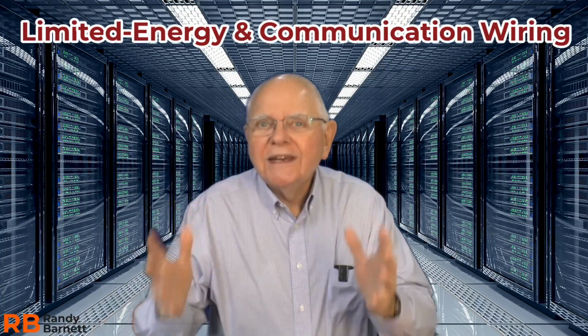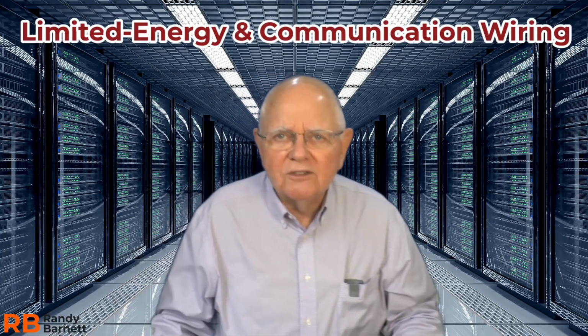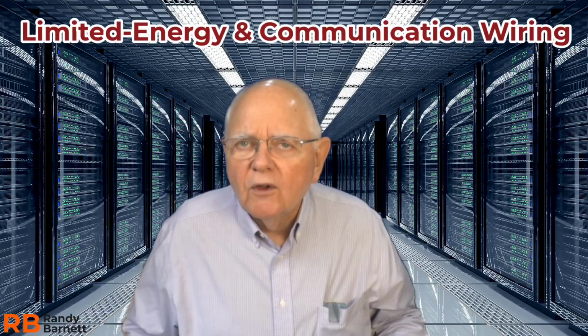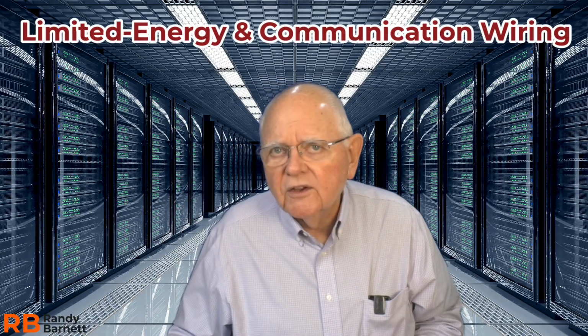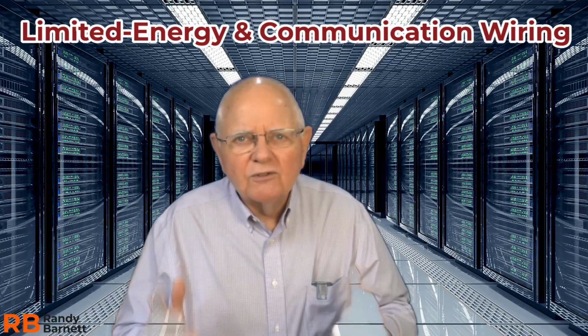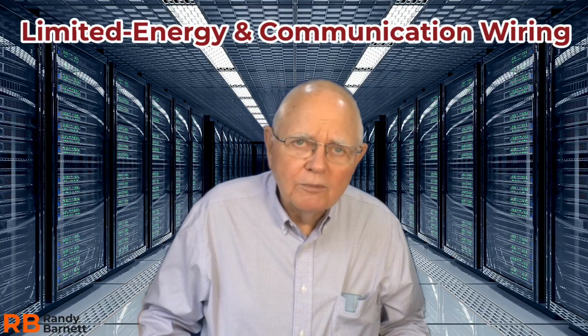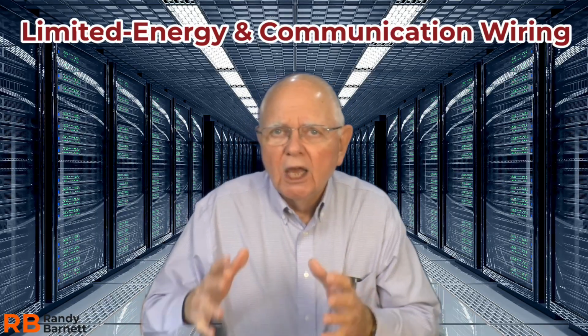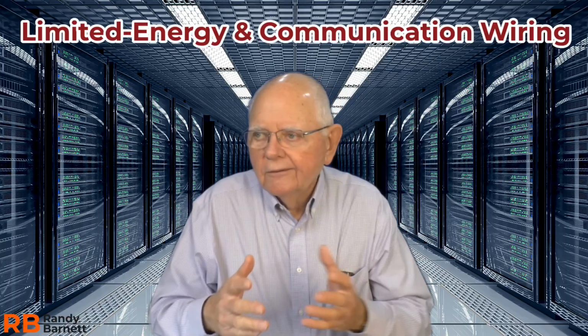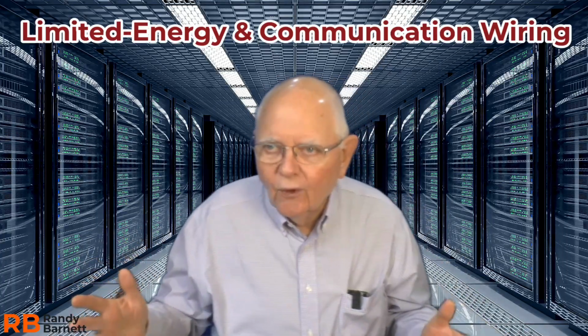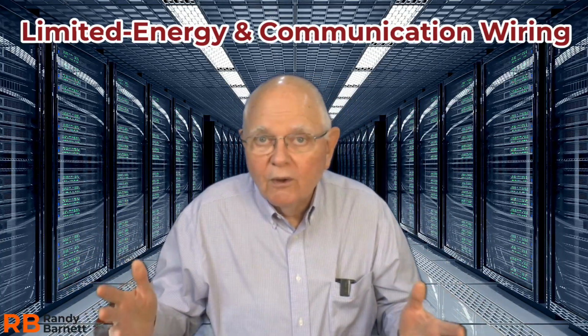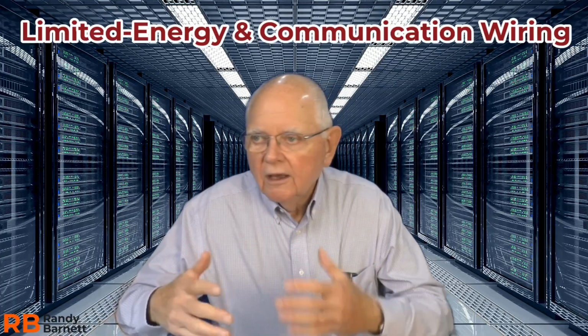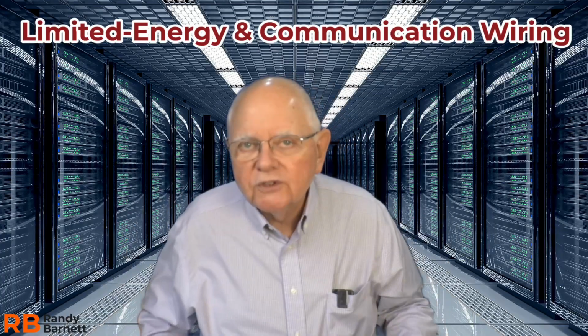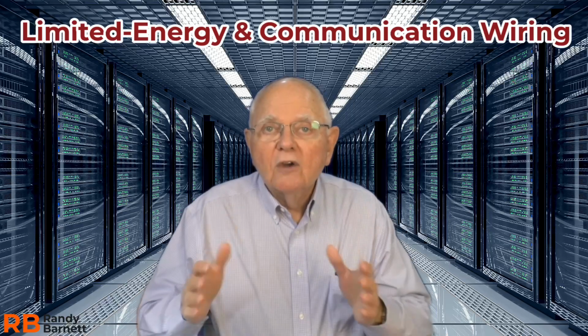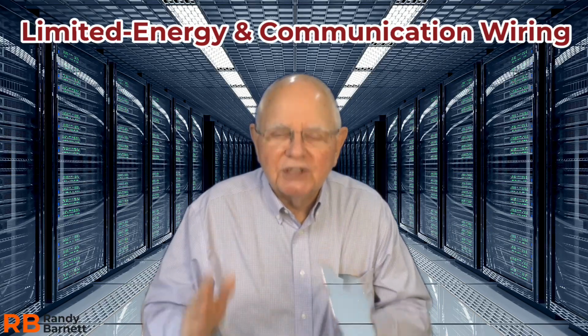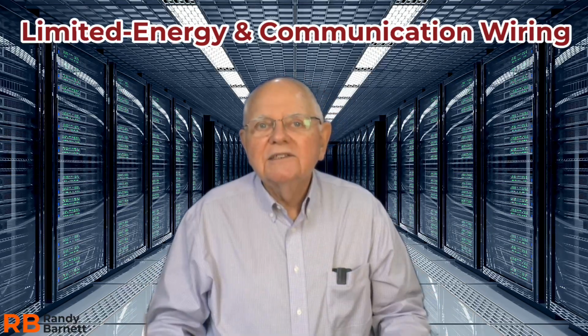In fact, we now have a definition for limited energy systems. I mentioned low voltage wiring because that's the way we talk out in the field, isn't it? But there's no definition in the code book. It doesn't differentiate between low voltage and whatever normal voltage 480 is, or 208 or 120, or a medium voltage and 4160 or high voltage or anything like that. Okay, what the code talks about is limited energy systems. So that's where we're headed today.